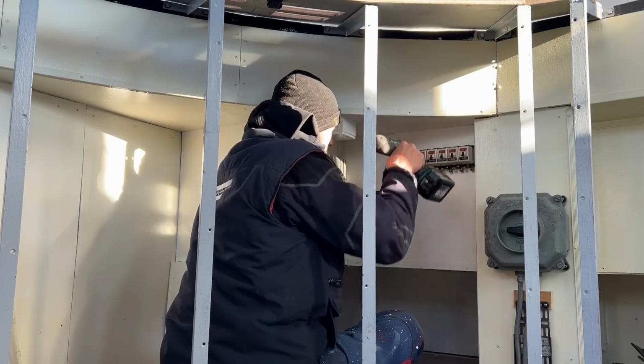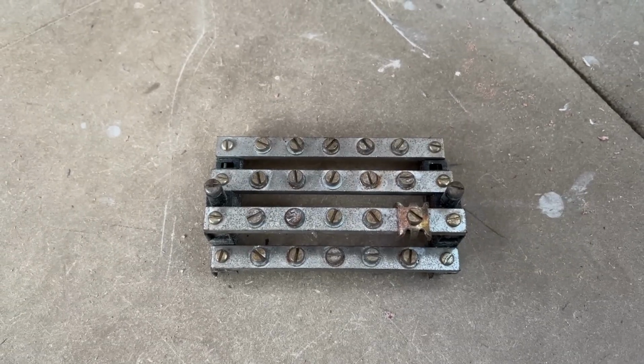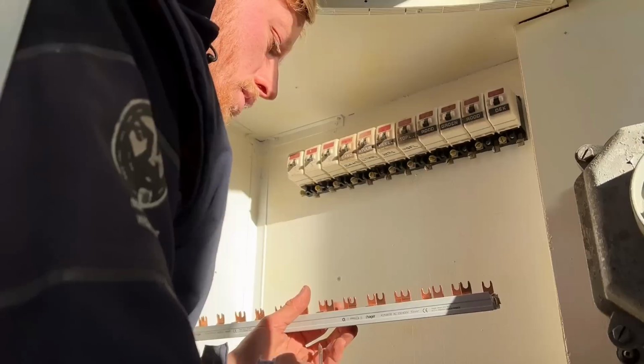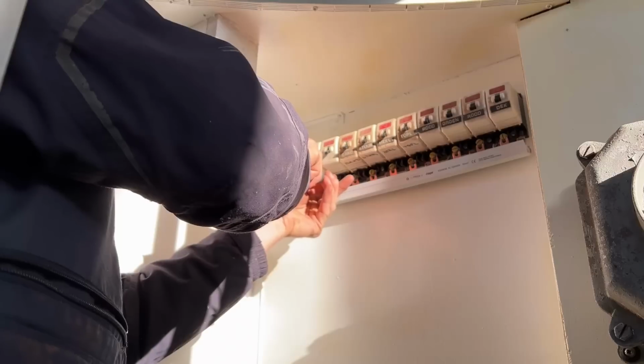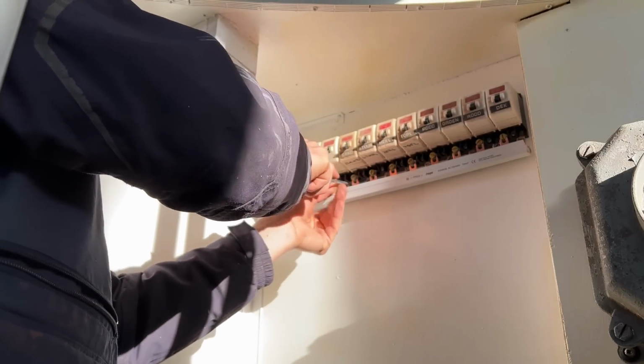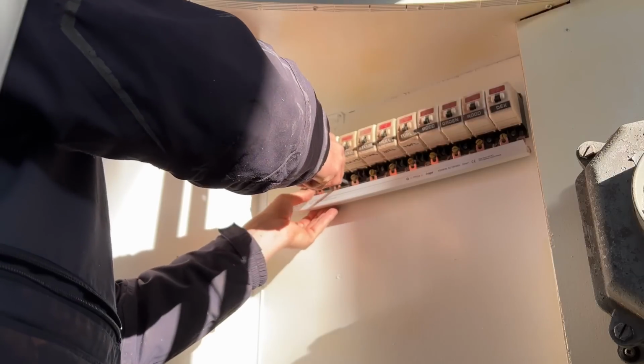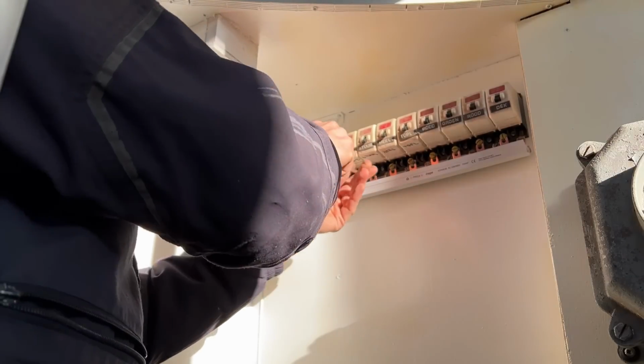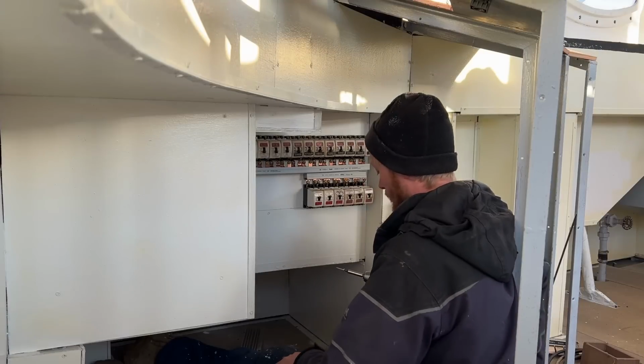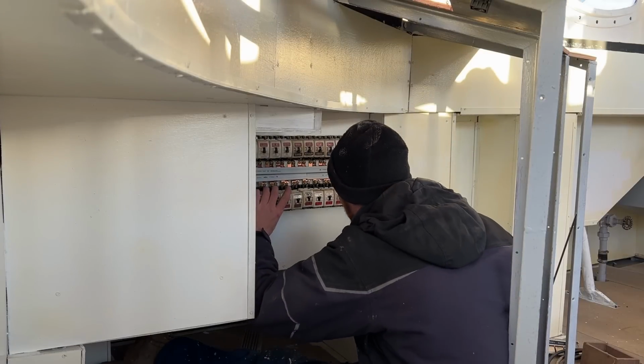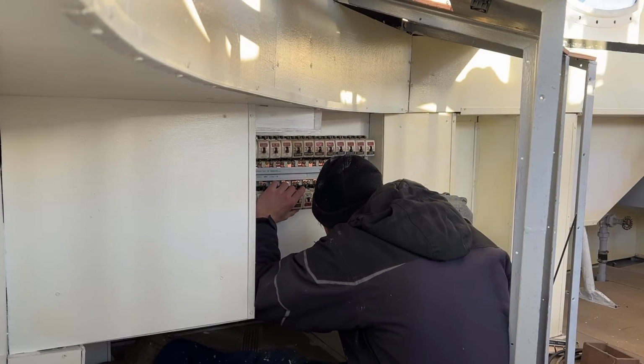On older installations, it's common that all these breakers are connected with a bare copper strip. Nowadays, that's considered a bit dangerous. And since we have some modern insulated forked bus bars left over that coincidentally exactly fit the old circuit breakers, we can create a safe switchboard using old parts. I'm installing more circuit breakers than we have use for at the moment, but future us will probably be thankful for that.